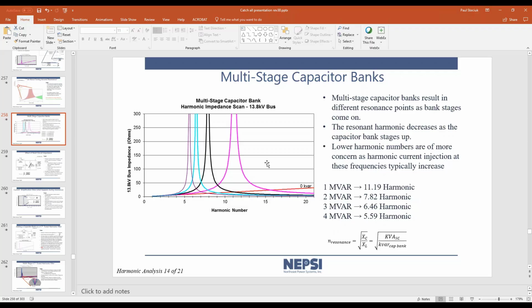So this is the sequencing or the staging on of capacitors within the network, and you can see in this situation that you have a resonance that might be over the 5th, and then another one that's slightly higher than 5th towards the 7th, and so on. So generally, as you add capacitors, you start off at a high frequency resonance, and then the resonant point decreases as a multi-stage cap bank comes online.